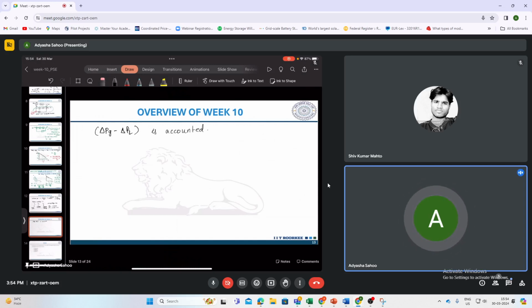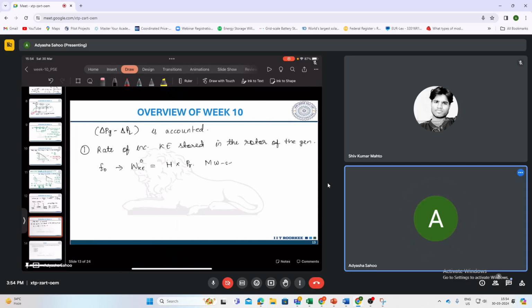So we see that it is accounted in two ways. Firstly, the rate of increase of kinetic energy stored in the rotor of the generator. So let's say at the nominal frequency F naught, the stored kinetic energy was WKE naught, and it was H times your PR in megawatt second. So H is your inertia constant and PR is your rated capacity of the generator. So PR is in megawatts and H is the inertia constant in seconds. So that is your WKE naught.